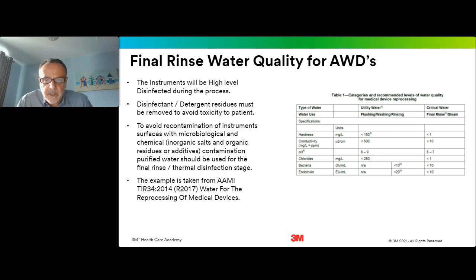But if you look at the critical water, which will be used for the final rinse, then the levels are much, much lower, and I would draw your attention particularly to the contamination levels with bacteria, less than 10 colony-forming units per mil, and endotoxins, again, less than 10 endotoxin units per mil.